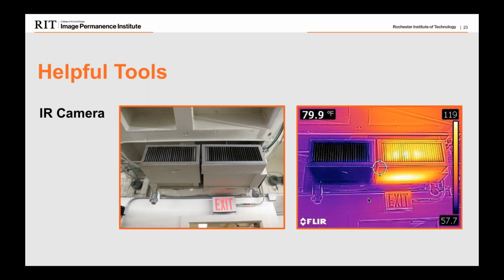Lastly, we worked with a museum a few years ago and went into their lobby, where their greatest concern was they could never get the lobby to a cool temperature. It was always very hot and uncomfortable in the wintertime, to the point where they almost shut the air handling unit down. We started imaging the space, and lo and behold, using the infrared camera, you could see through the floor the outline of the boilers. All that heat from the boiler heating the space below was coming straight up through the floor and warming the room above.